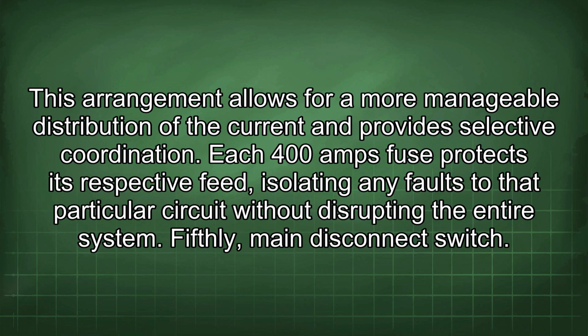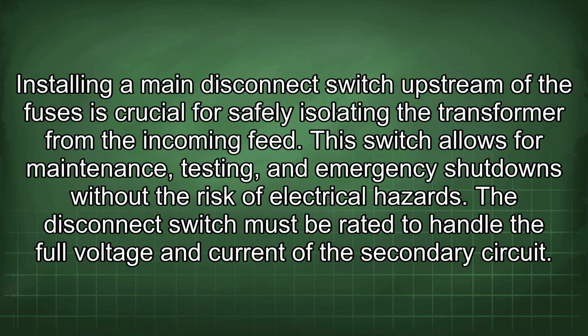Fifthly, main disconnect switch. Installing a main disconnect switch upstream of the fuses is crucial for safely isolating the transformer from the incoming feed. This switch allows for maintenance, testing, and emergency shutdowns without the risk of electrical hazards. The disconnect switch must be rated to handle the full voltage and current of the secondary circuit.